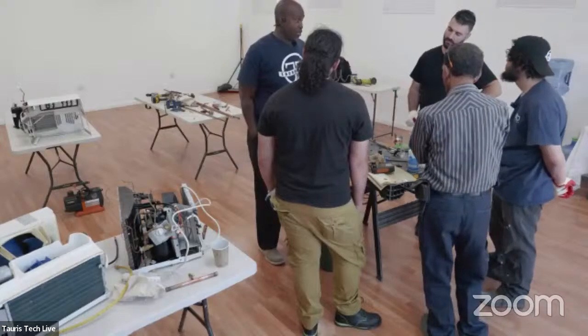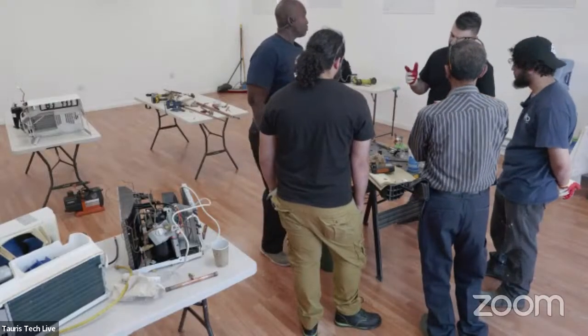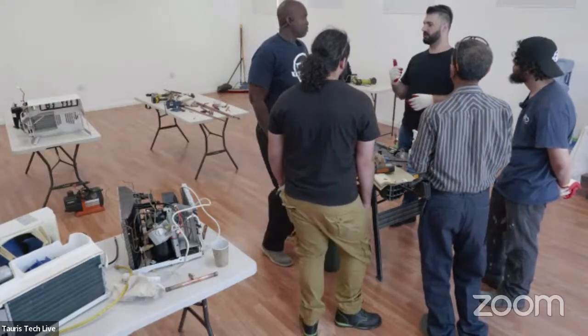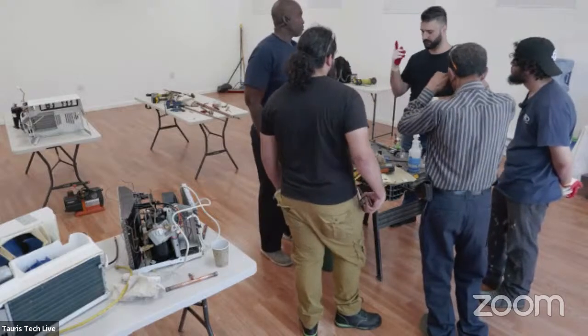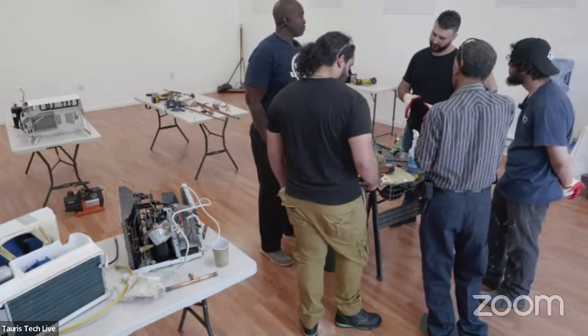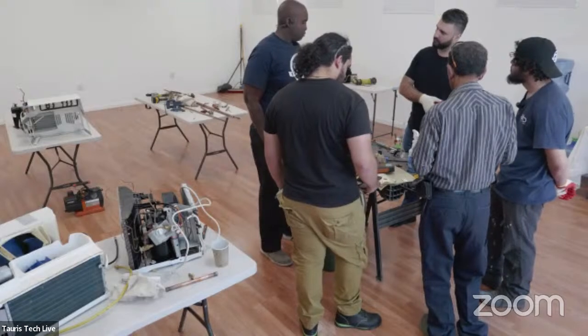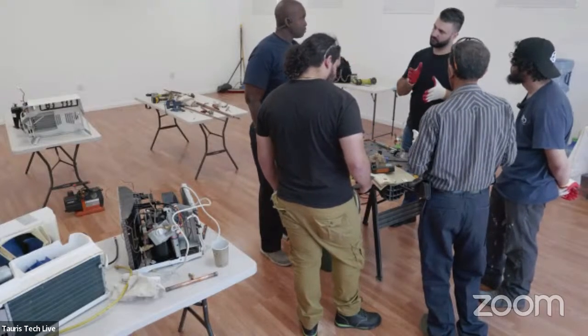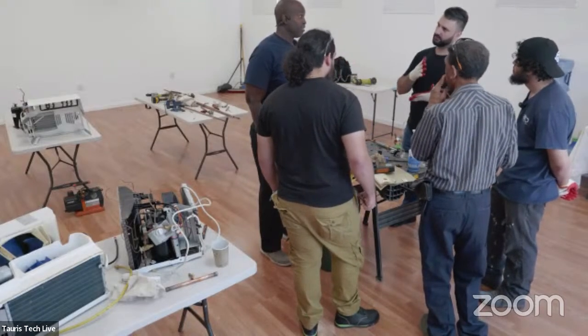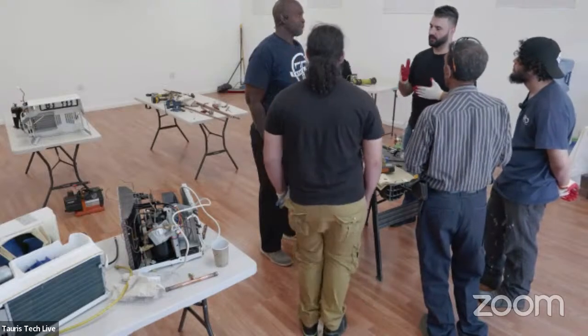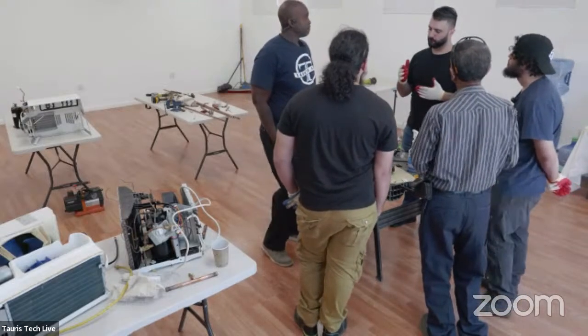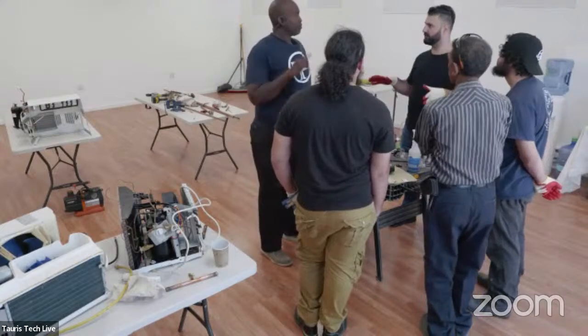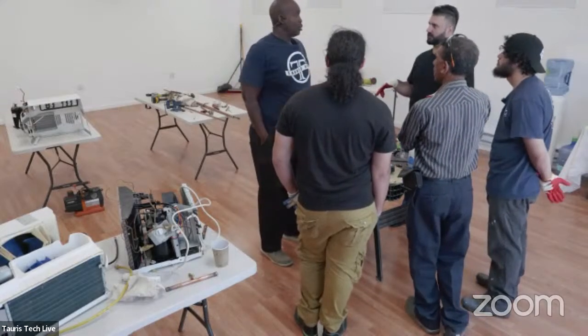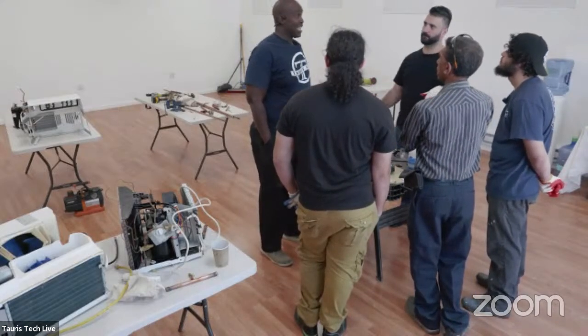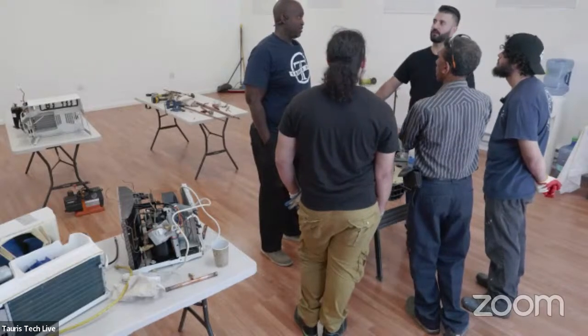And last week when we were pulling a vacuum in the unit, I forgot to ask. You were going with the micron gauge. So you said 500 microns. That's where you want to pull it. Yes. And can that move? Let's say you're done with the vacuum and the micron gauge. It has to stay at 500 microns.